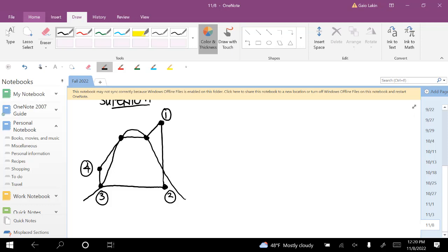There's also benefit to heating this up past the critical point. But that's not what this is necessarily. This is the idea that it goes past the saturation point. One of the reasons you want to do that, practically speaking, is it does a lot of damage to the turbine if you have a liquid mixture in there. It's very hard on the turbine blades. And so the fewer liquid droplets you have, the better it is for the system.